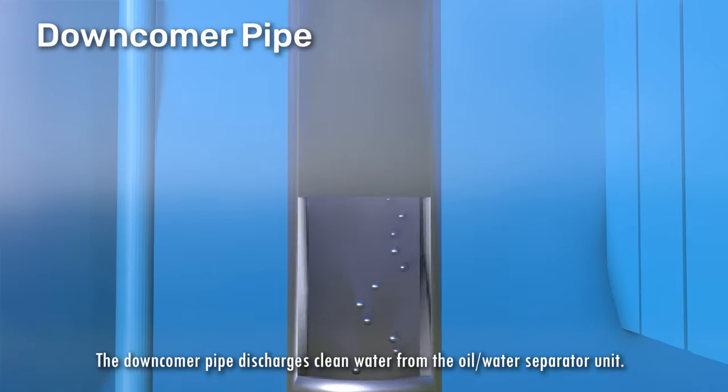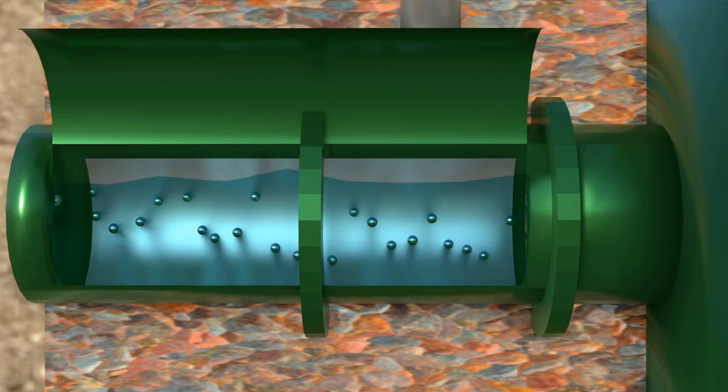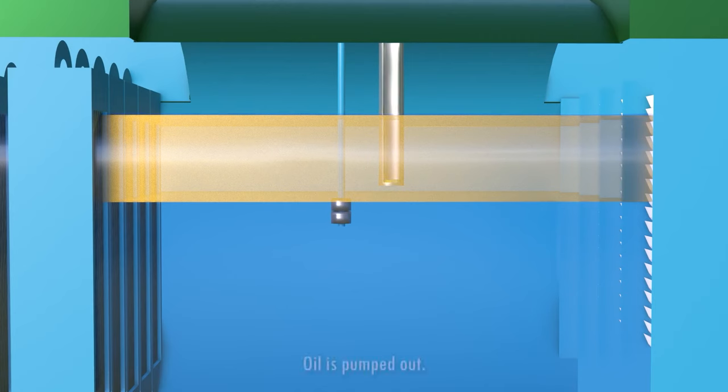Flow is moving through the downcomer pipe on the outlet. That is set at 20% off the bottom of the vessel, so clean water is flowing out while we're trapping oil on top of the water and solids at the bottom on the front end.